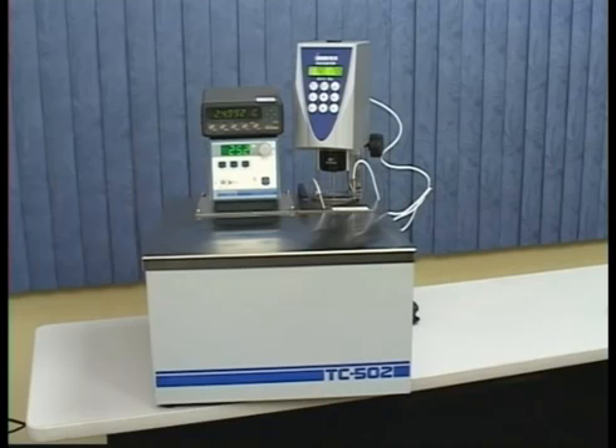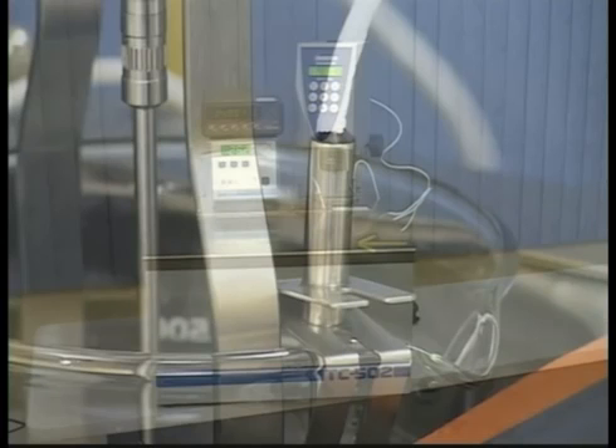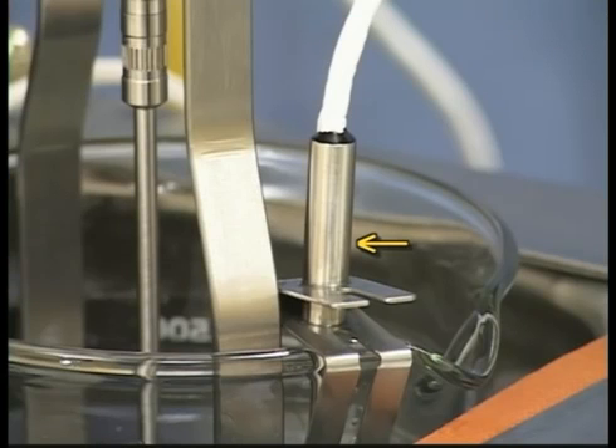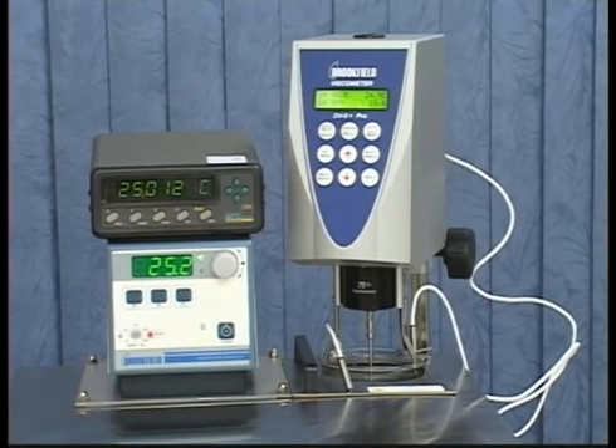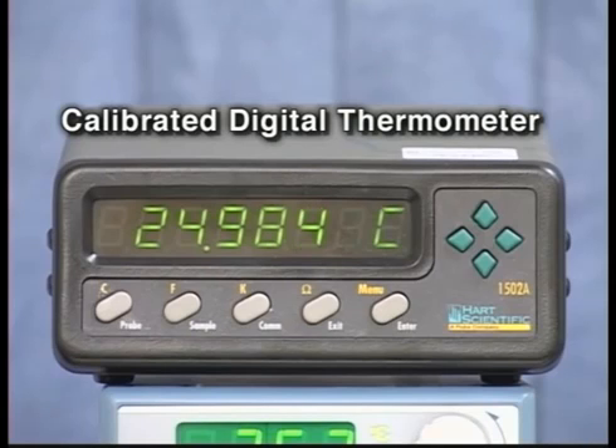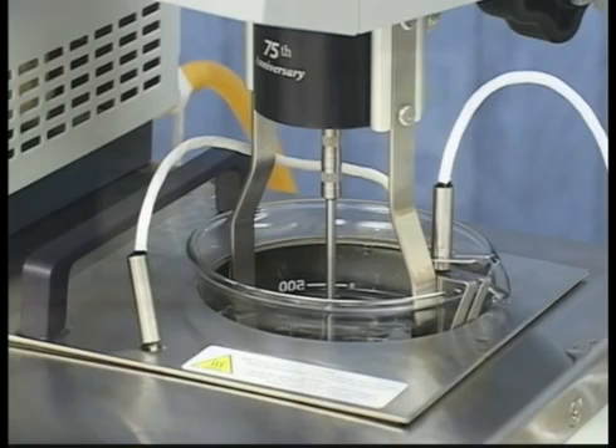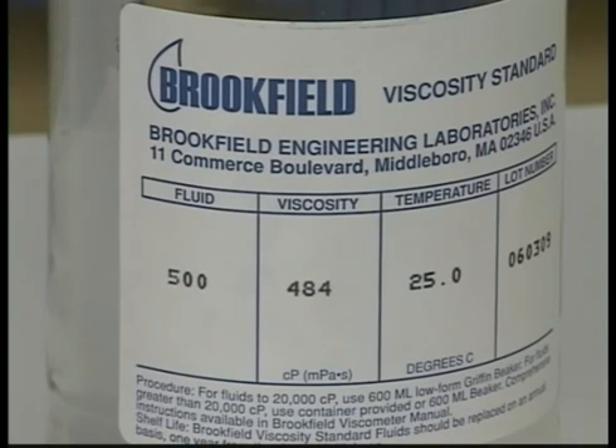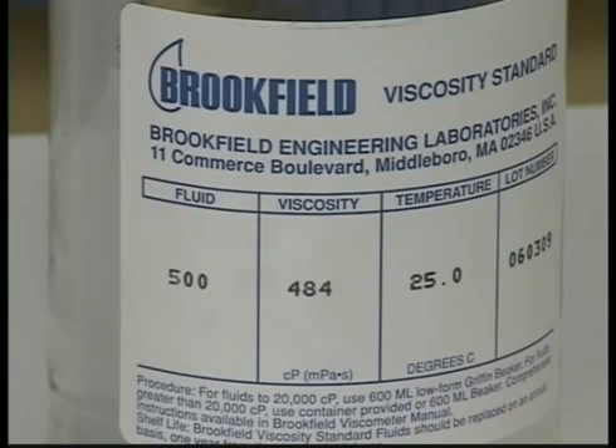The viscosity standards are very sensitive to temperature. The temperature probe on the Brookfield viscometer is accurate to plus or minus 1 degree centigrade. To ensure proper temperature equilibration and accuracy for the viscosity standard, use a calibrated thermometer with higher accuracy. The temperature of the viscosity standard should be controlled at 25.0 degrees centigrade, plus or minus 0.2 degrees centigrade. The thicker the fluid, the longer it will take to equilibrate. For this 500 centipoise fluid, approximately 1 hour should suffice.